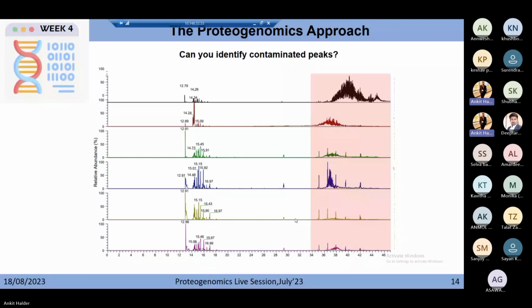If there are certain peptides or things more hydrophobic than your peptides, or certain peptides in the carryover that get eluted suddenly, you will get distorted peaks, which show that it is contamination, and it goes away after cleaning up your systems. Is that clear? Yes, sir.